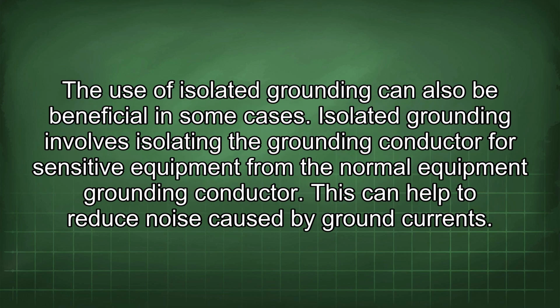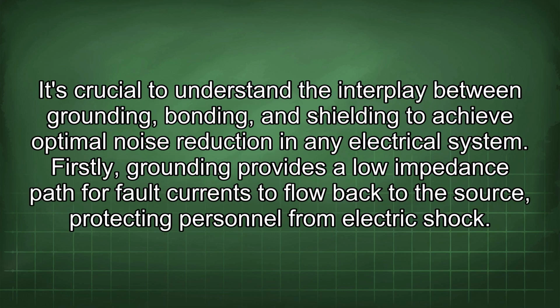The use of isolated grounding can also be beneficial in some cases. Isolated grounding involves isolating the grounding conductor for sensitive equipment from the normal equipment grounding conductor. This can help to reduce noise caused by ground currents. It's crucial to understand the interplay between grounding, bonding, and shielding to achieve optimal noise reduction in any electrical system.